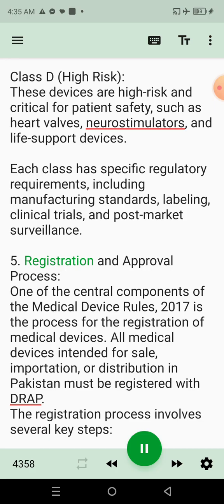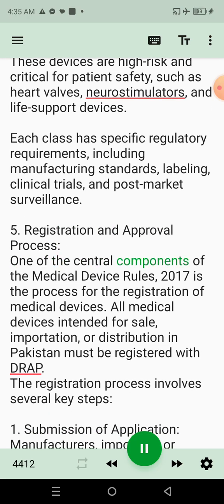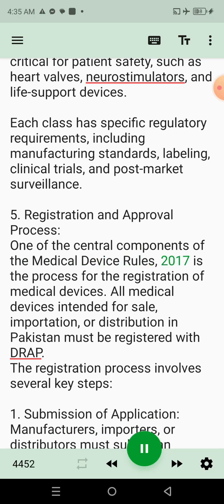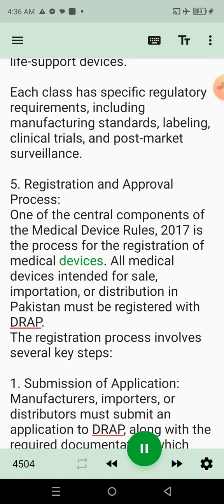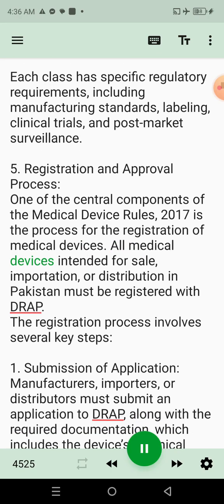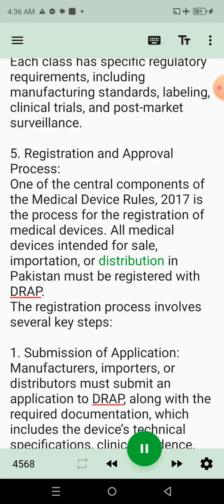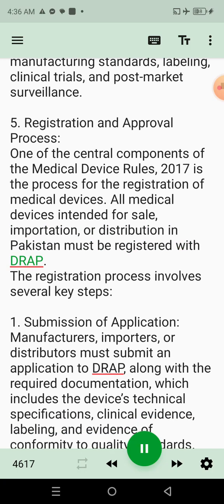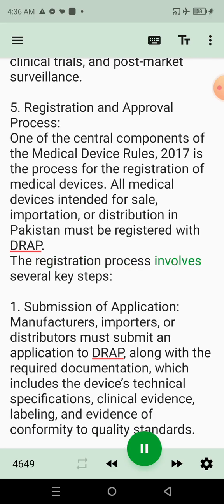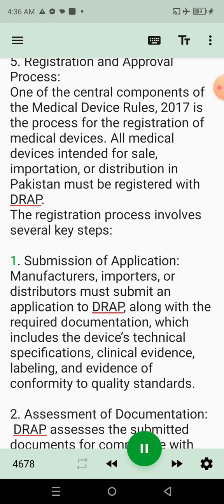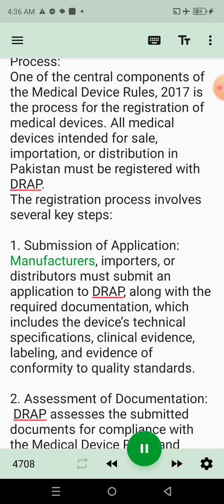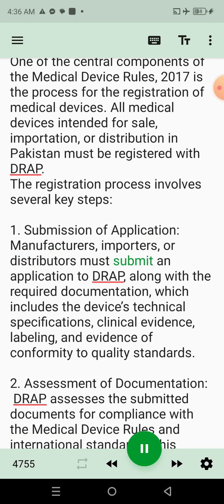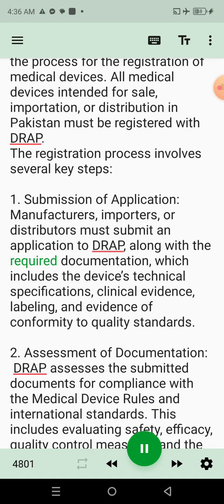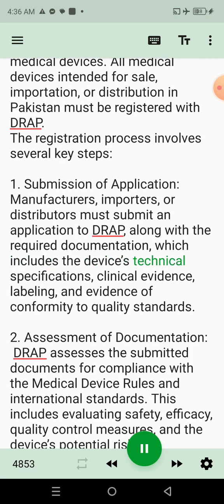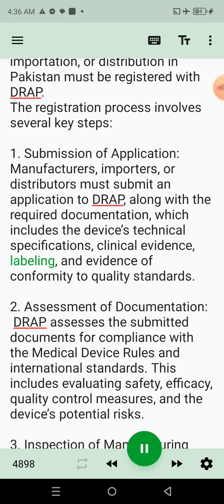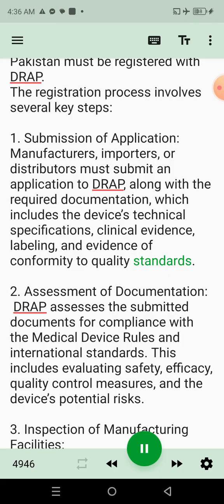5. Registration and approval process. One of the central components of the Medical Device Rules, 2017 is the process for the registration of medical devices. All medical devices intended for sale, importation, or distribution in Pakistan must be registered with DRAP. The registration process involves several key steps. 1. Submission of application. Manufacturers, importers, or distributors must submit an application to DRAP, along with the required documentation, which includes the device's technical specifications, clinical evidence, labeling, and evidence of conformity to quality standards.